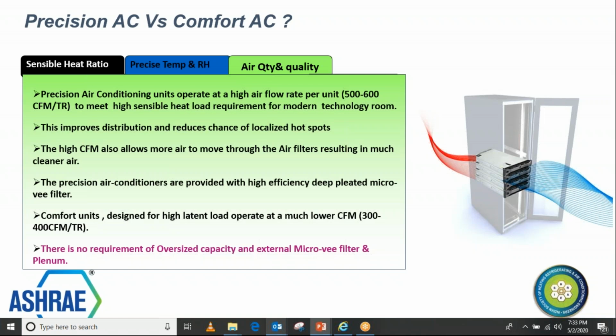Now, having more CFM per TR helps you transfer the heat faster, and at the same time it automatically also keeps the equipment clean, other than the effect of the high filtration in the precision air conditioning system. In comfort ACs, it is typically 300 to 350 CFM per TR, and there is a huge difference from 300 to 600 CFM per TR. So imagine on 1 TR, this is the difference. If you have to install 10 TR capacity, you land up having very less sensible capacity and very less CFM per TR compared to precision AC equipment.